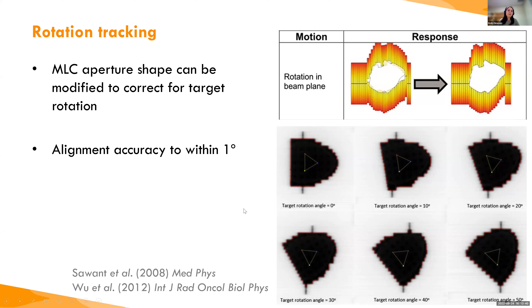Here are some example images from an experimental implementation of this. You can see how the MLC aperture gets rotated to match the rotation of the target. Note that it's not the collimator that's rotating in these images, it's actually the MLC leaf positions that are recreating these rotated shapes. Through this rotational MLC tracking, they found that the accuracy could be aligned to the target within a degree.